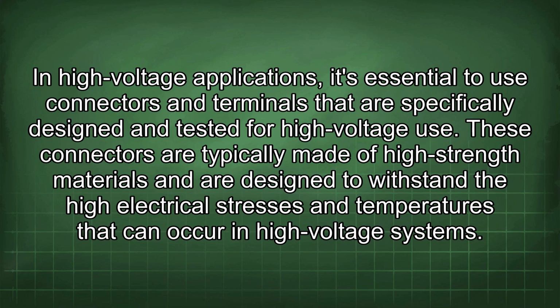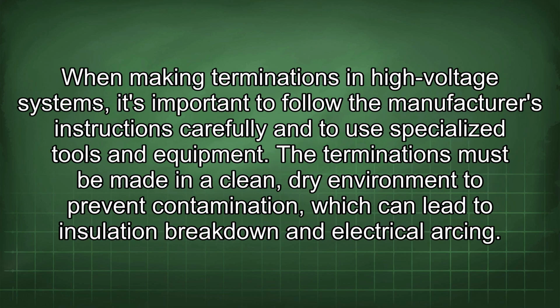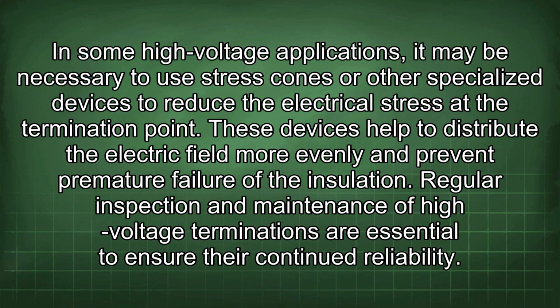These connectors are typically made of high-strength materials and are designed to withstand the high electrical stresses and temperatures that can occur in high-voltage systems. When making terminations in high-voltage systems, it's important to follow the manufacturer's instructions carefully and to use specialized tools and equipment. The terminations must be made in a clean, dry environment to prevent contamination, which can lead to insulation breakdown and electrical arcing. In some high-voltage applications, it may be necessary to use stress cones or other specialized devices to reduce the electrical stress at the termination point. These devices help to distribute the electric field more evenly and prevent premature failure of the insulation.